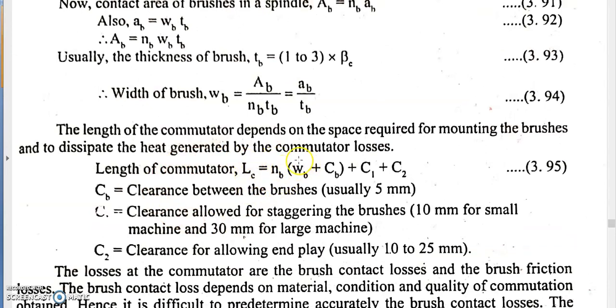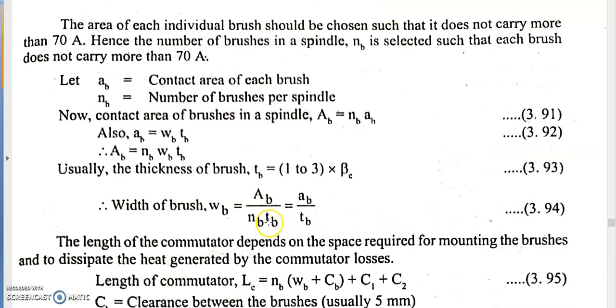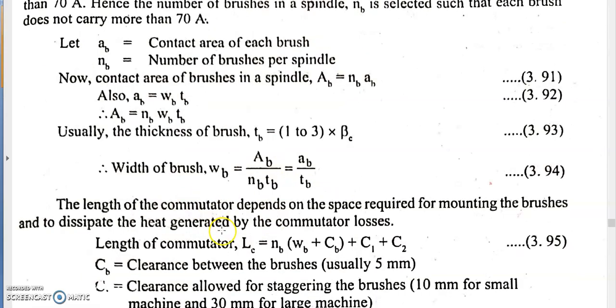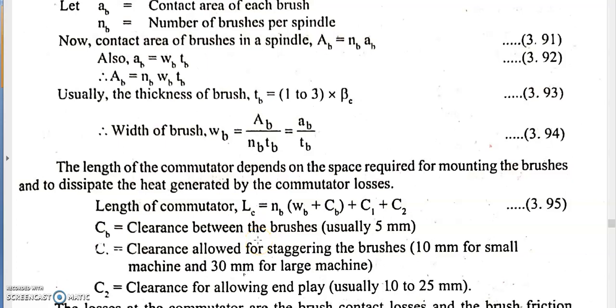The clearance values are: CB equals 5 mm between brushes; C1 is the clearance allowed for staggering the brushes — 10 mm for a small machine and 30 mm for a large machine; and C2 is the clearance for the end play, which is 10 to 25 mm. All these clearance values are known. The number of brushes is calculated from the current criteria, and the width of the brush is calculated from the thickness criterion, enabling us to compute the commutator length.